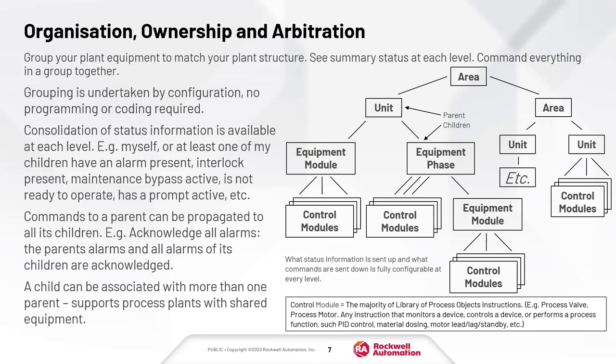Organization, Ownership and Arbitration allows the system implementer to group the plant equipment together to match your plant structure, and then obtain status information at each level and command groups of things in your plant from this location. It also gives you advanced diagnostic features, which we'll demonstrate a bit later in this video. In the example you can see here, we have grouped items in our plant into areas, and in those areas you can also have other areas, units, equipment modules, phases, and control modules. There are no rules about what has to be underneath what.